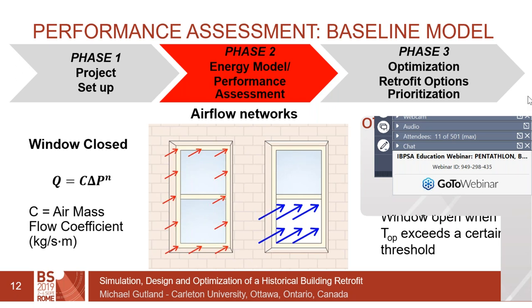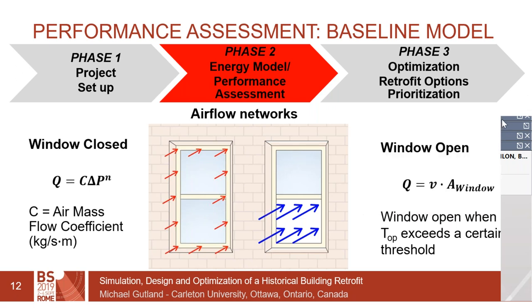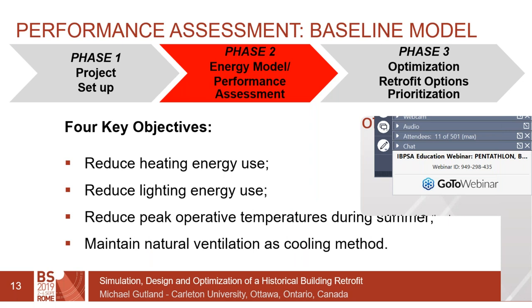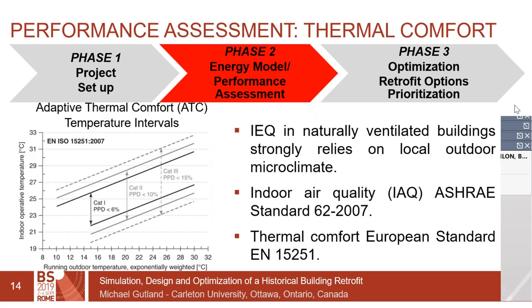We chose three to six air changes per hour as appropriate for a building of this age and construction. Based on this, we identified four key objectives: number one, reduce heating energy use; number two, reduce lighting energy use; number three, reduce peak operative temperatures during summer; and number four, maintain natural ventilation as a cooling method rather than introduce a mechanical system. We used operative temperature as the basis for all occupant comfort assessment.